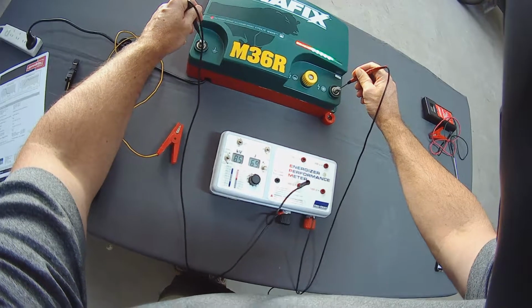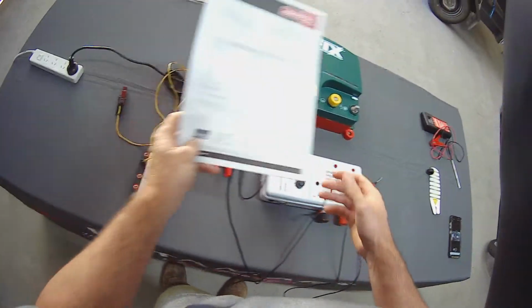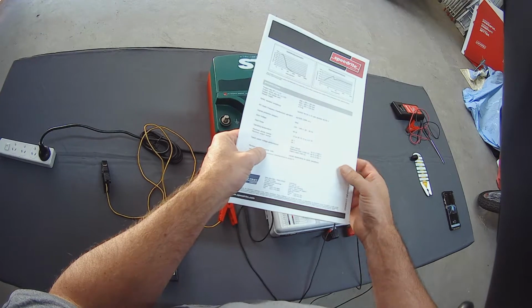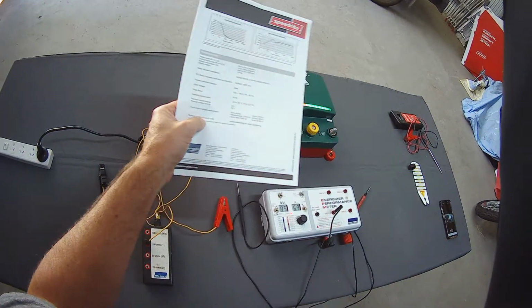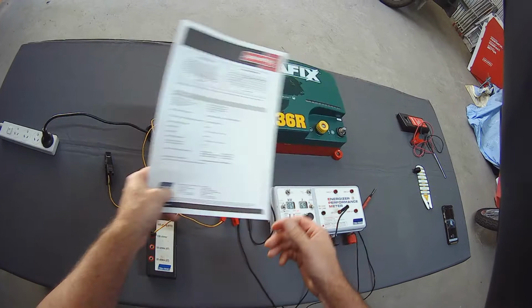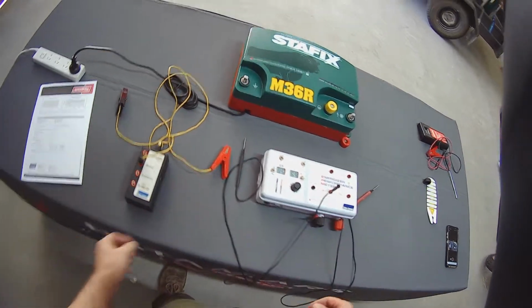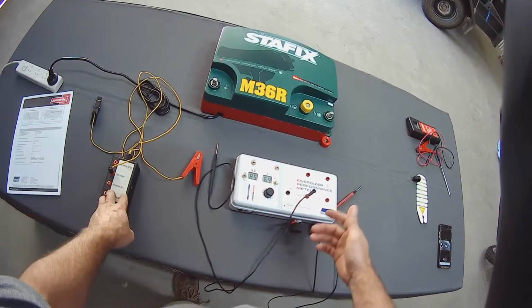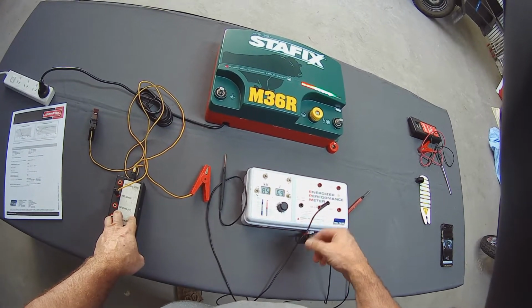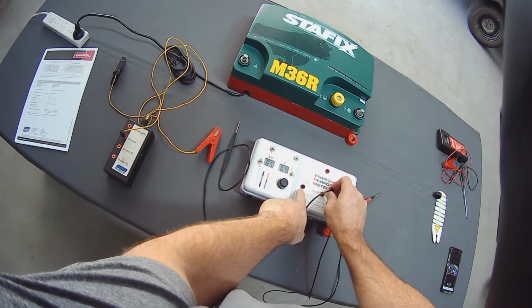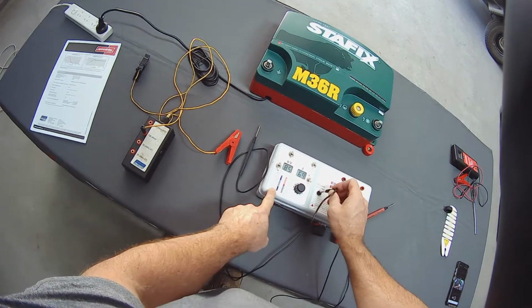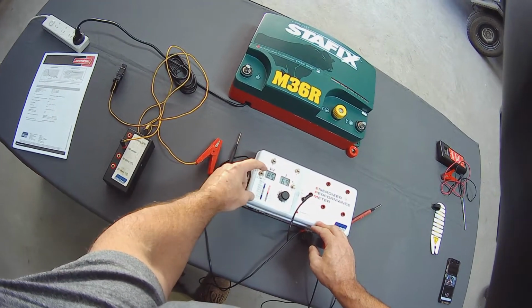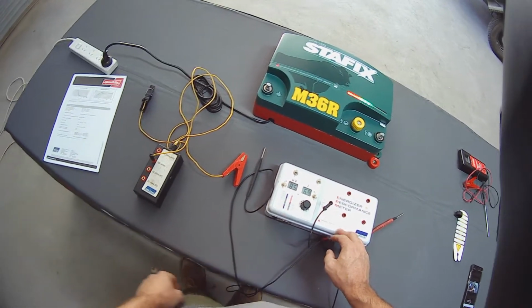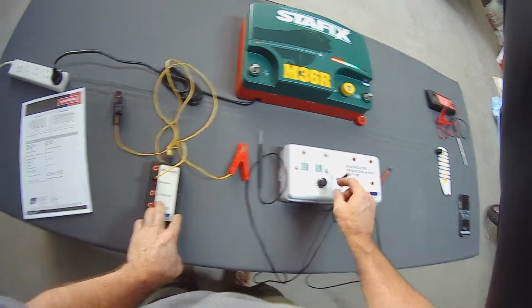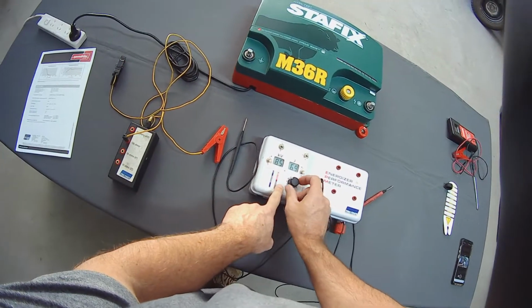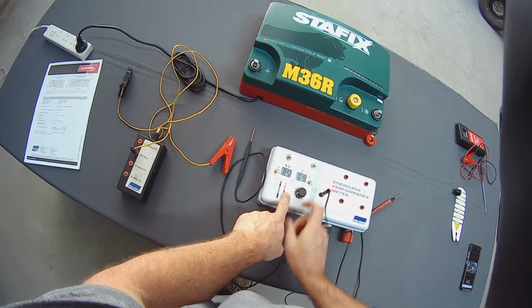At a 500 ohm load, once again, if we look at our spec sheet, 500 ohms, we should be 8.5, which is spot on to what we've got. So if we put a bigger load on that, we need to use the external load box because this Energiser is above 12 joule output. So our probe goes in our no load or external load box port. This switch goes to load range 2, which is our external load box, and we're going to put 100 ohms on it so we can turn our dial to 100 ohms.